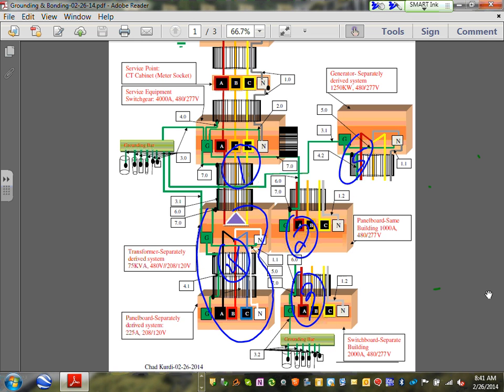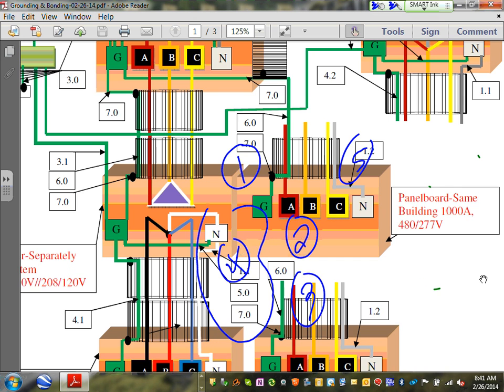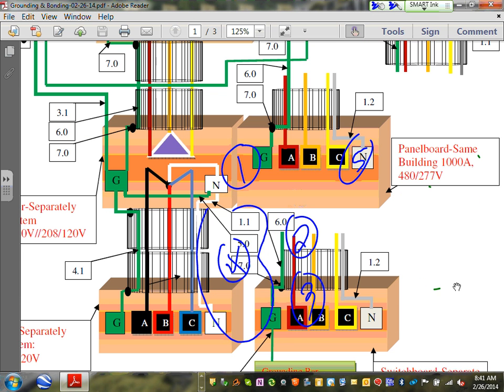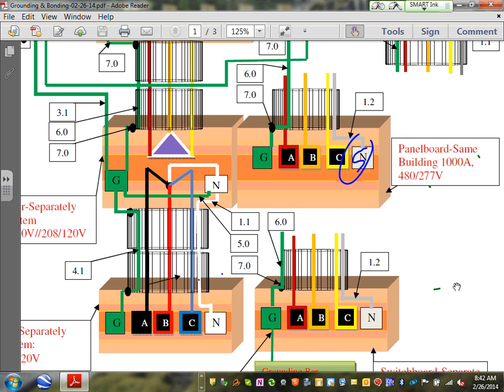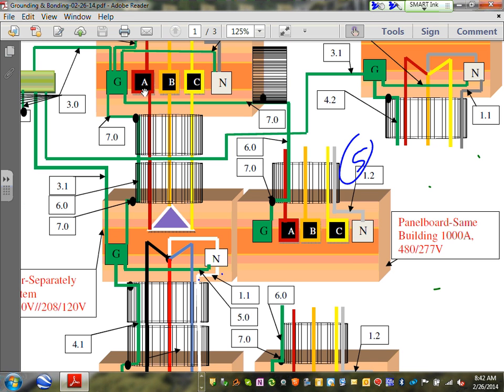So let's go ahead and expand this one a little bit so we can see what we're doing. Okay, I'm going to walk you guys through this, if you don't mind. Derek, my friend, here's what happened. We need to go right from the switchgear. Look what happened. From the switchgear, can you guys see that? From my switchgear, I brought the feeder through conduits to a panel. With that feeder, you have to have something called 7.0, Adam. 7.0, that's an equipment grounding conductor between that switchgear and the transformer. That's called an equipment grounding conductor. Very simple, right?